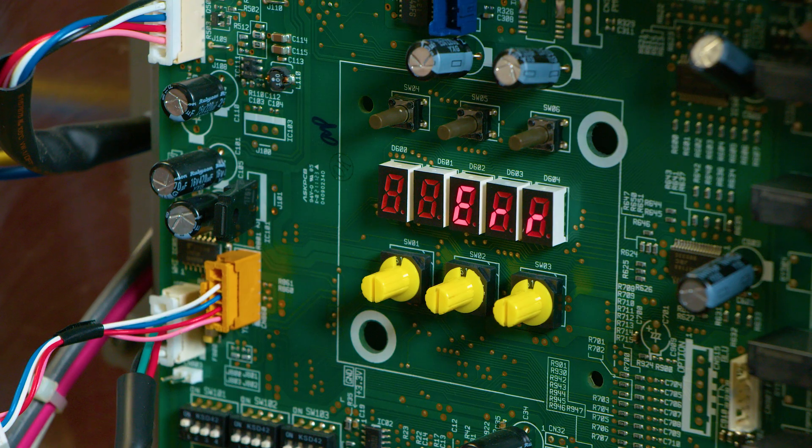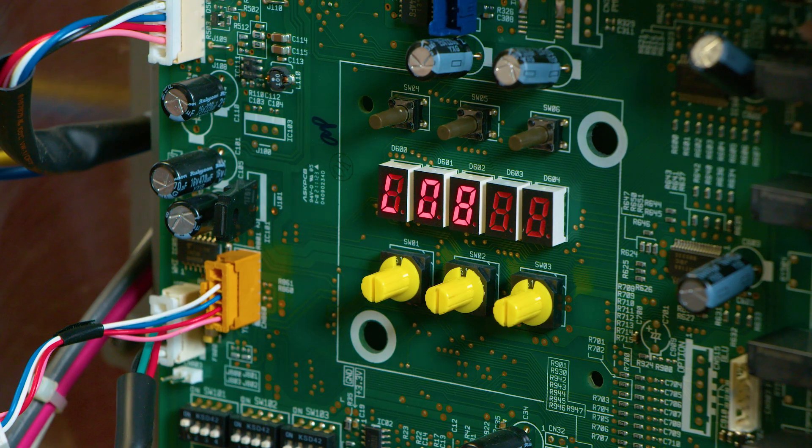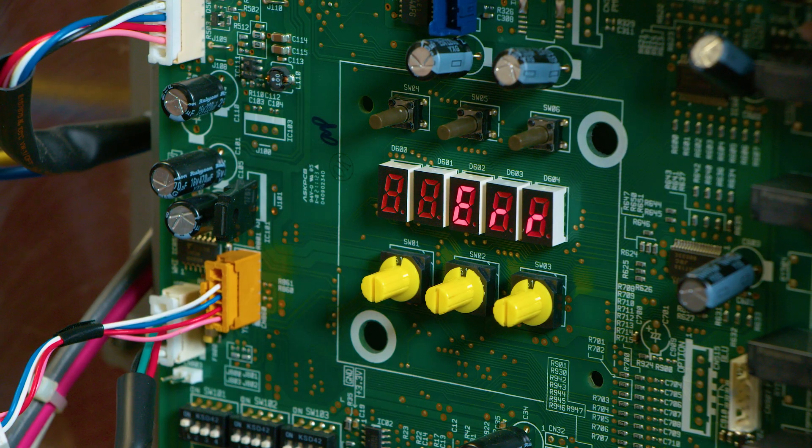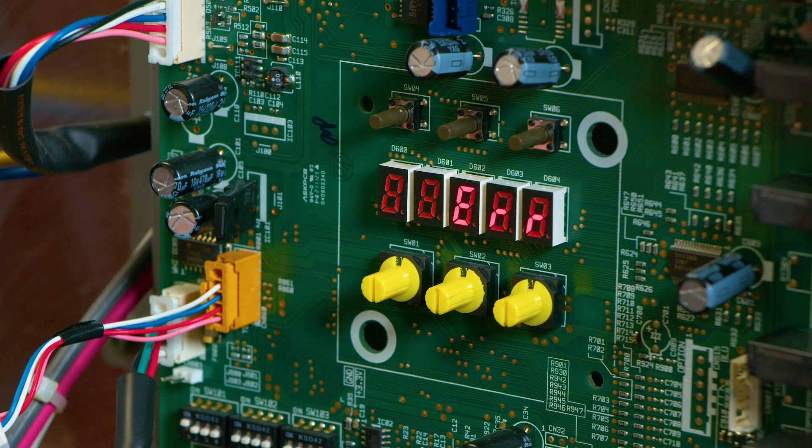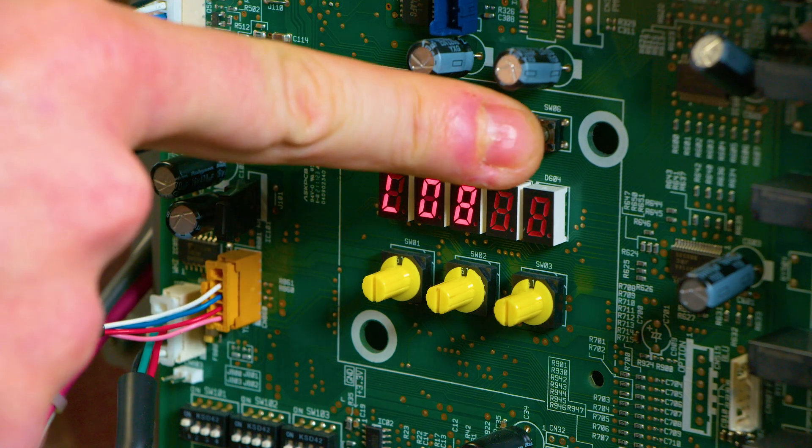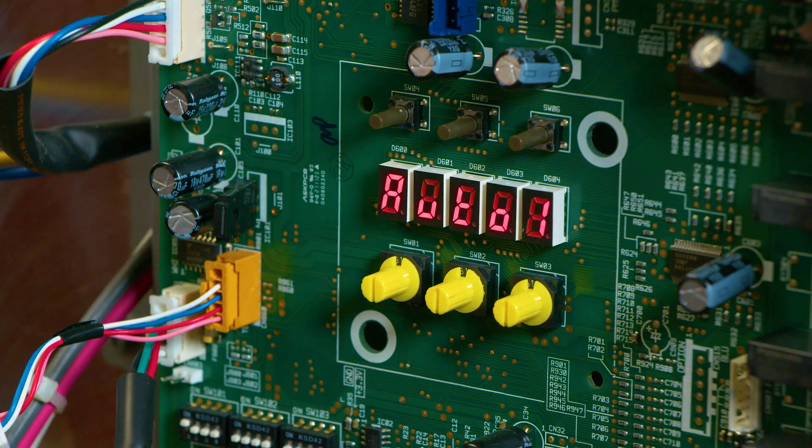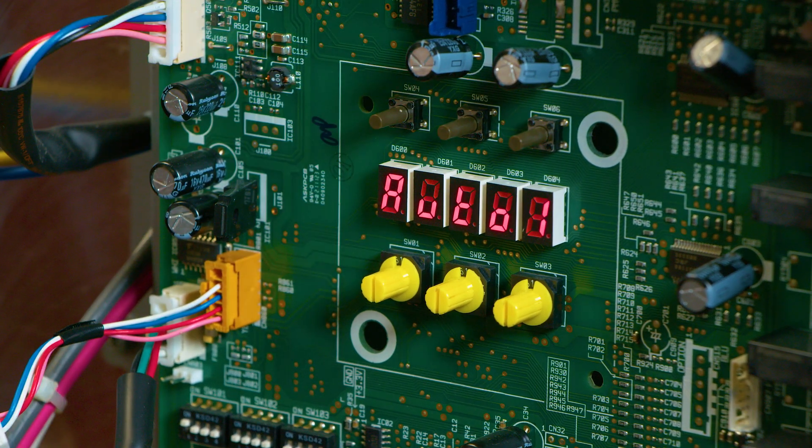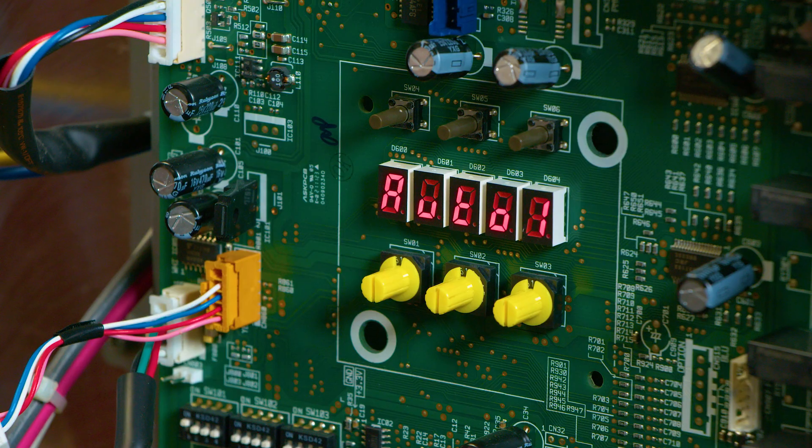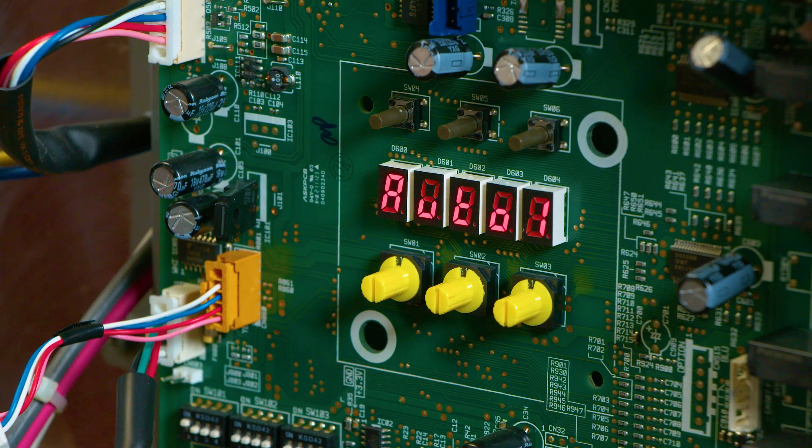By pressing SW06, which is also located above the rotary dials, we will see AUTO1 appear. The system will now count from AUTO1 to AUTO9. This does not reflect how many indoor units are connected.